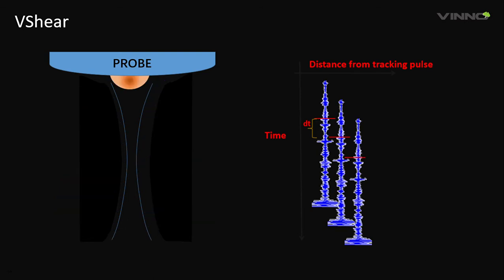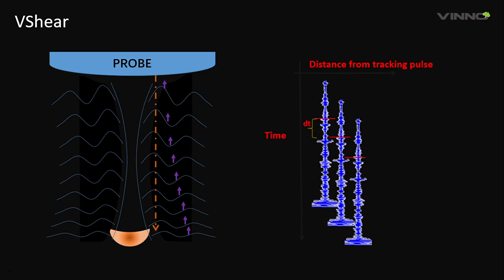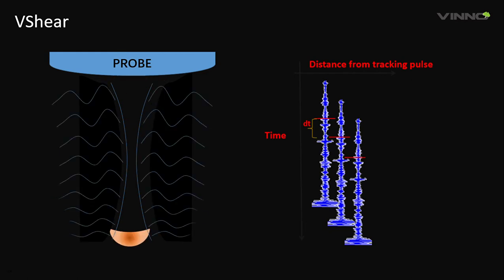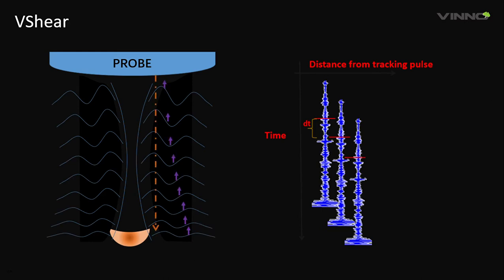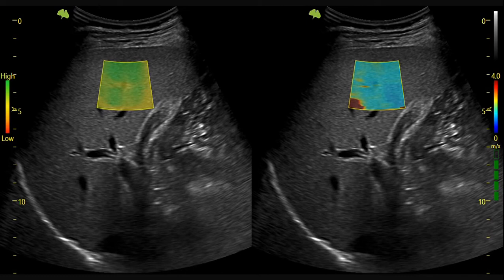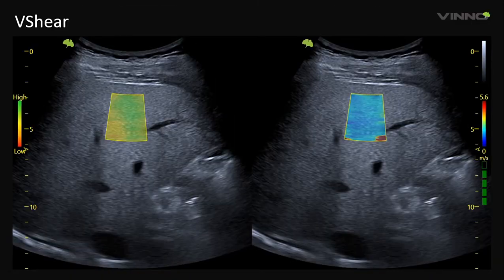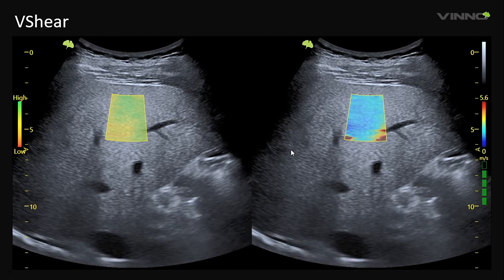These tissue movements in turn produce shear waves. The generated shear waves propagate perpendicular to the direction of the push pulses, typically between 1 to 10 meters per second. Tracking ultrasound pulses — with an average tissue propagation velocity of 1540 meters per second — track the propagating shear waves and estimate their velocity. Stiffer tissues tend to propagate shear waves faster than soft or elastic tissues. The resulting dispersion of shear wave velocity over a 2D area is displayed as a parametric color map on the real-time 2D image, with the shear wave velocity map on the right and the reliability map on the left.